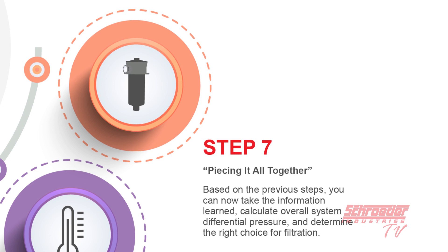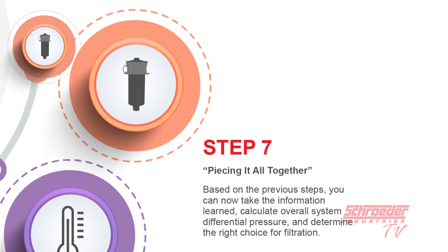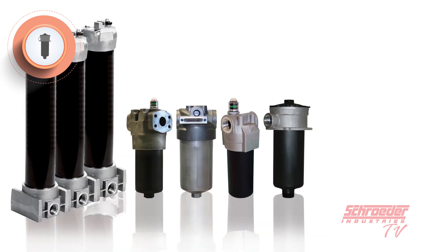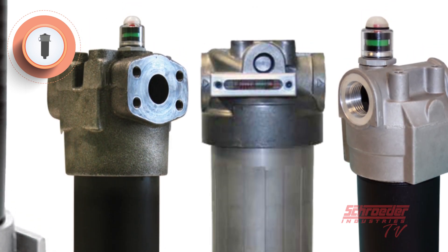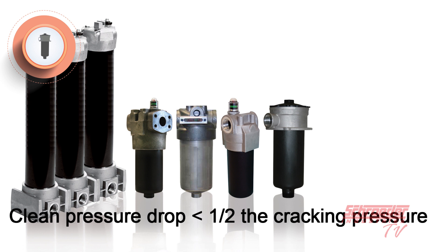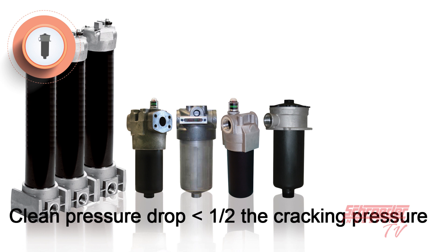Step seven is to piece it all together. With all the information gathered from steps one to six, you can calculate the overall system differential pressure. If all pieces come together correctly, your solution should result in your clean element pressure drop being less than half of the overall bypass cracking pressure at normal operating temperature and flow. Remember to note the porting options you need for your specific system and if you would like any contamination indicator options too.